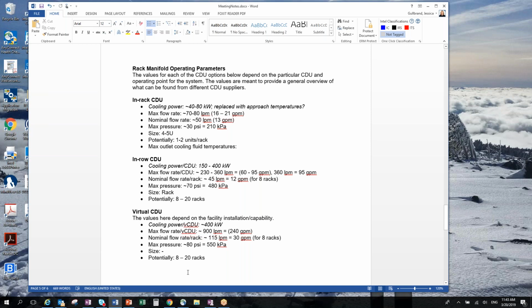I have a question on this virtual CDU. Is the assumption that the primary side pumping system will basically serve as the CDU, and the fluid is directed to the racks directly? Yes, through a so-called virtual CDU, you control the flow to the racks directly from the primary side. So there's not a secondary fluid and primary fluid, there's only one. So it's just some sort of flow modulation system, but there's no plate heat exchanger or heat exchange in the middle? No.